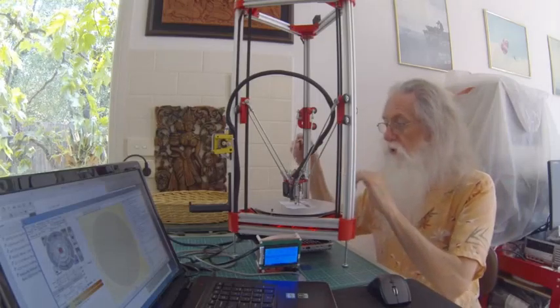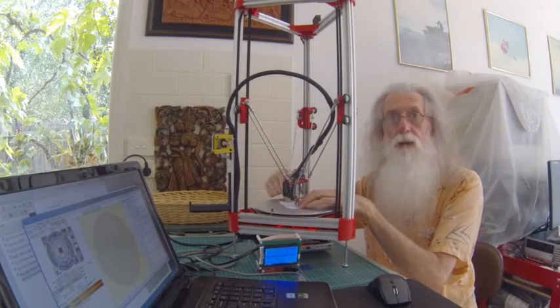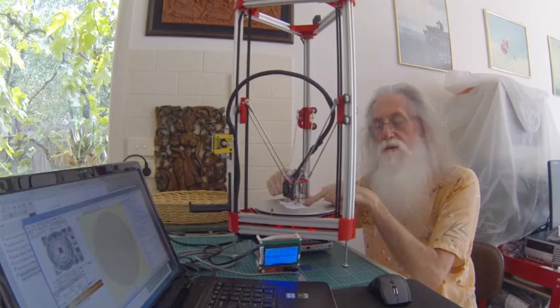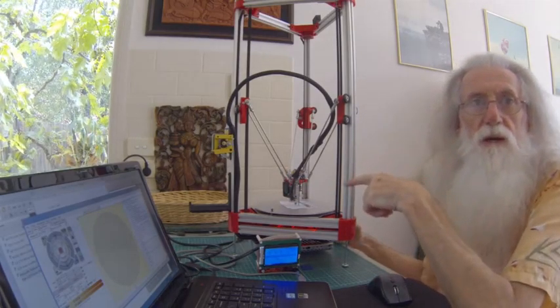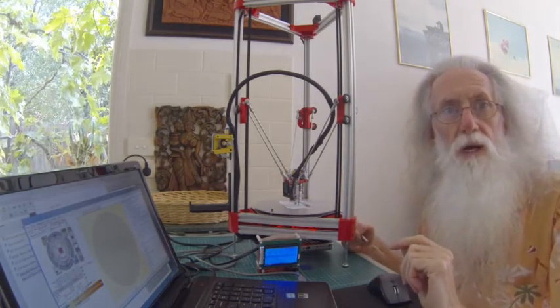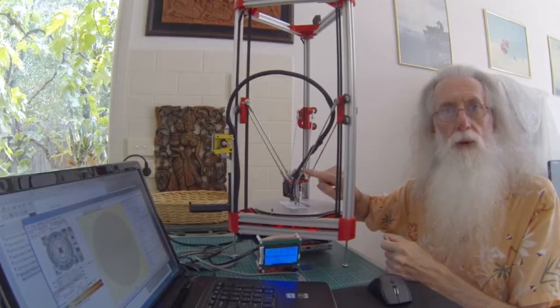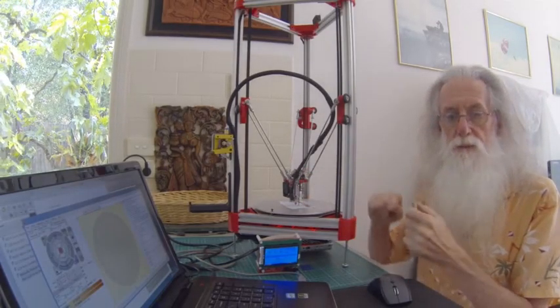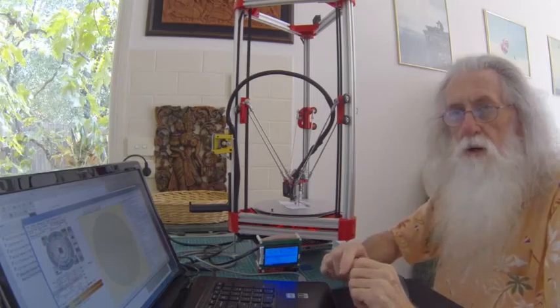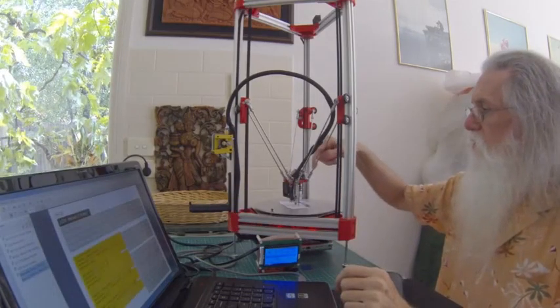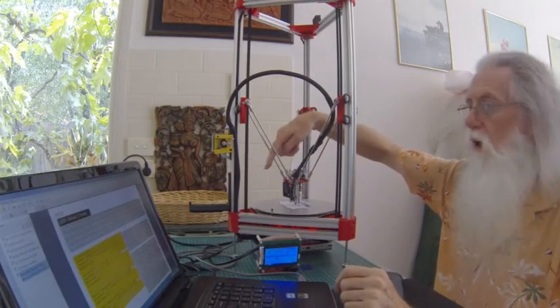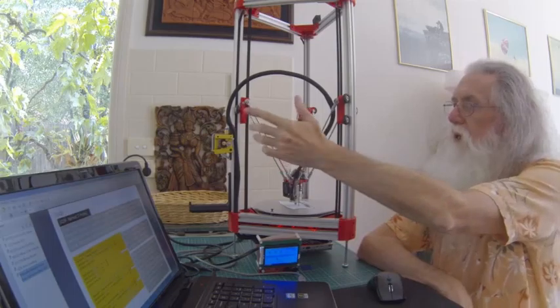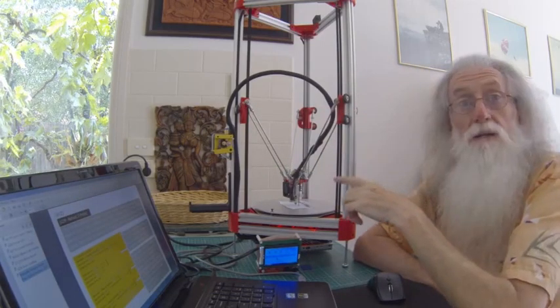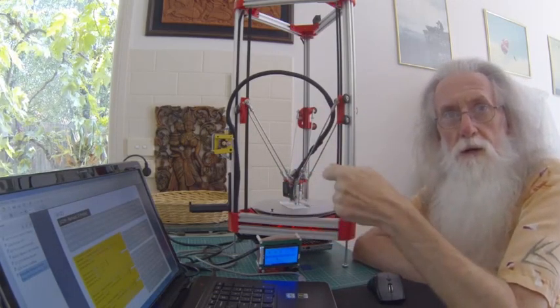You do it in a dark room, and then you just move the paper till the cross is lined up with the dot. That gives you your zero table position. But also while you're there, unlock your probe and lower it onto that same piece of paper. The reason is that the other manual tells you to put the probe on the Z column face. Our manual, the Centron, didn't, and I put it there to get the cable away from the wall and all this sort of stuff. So that's an alternative I didn't choose.